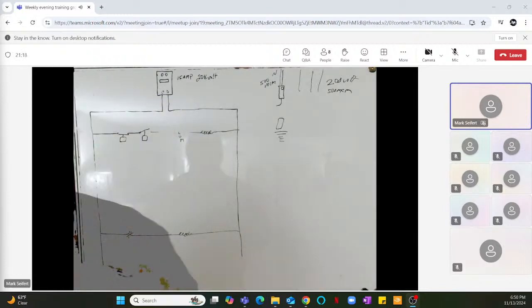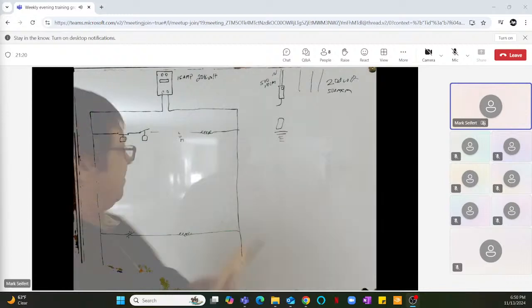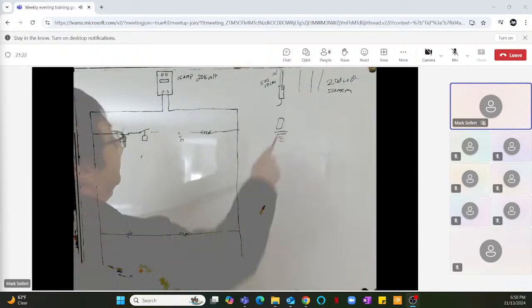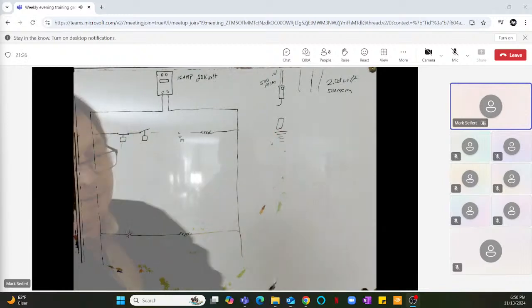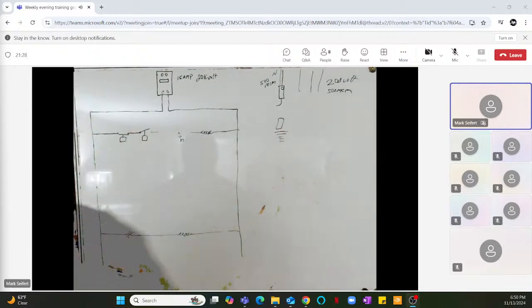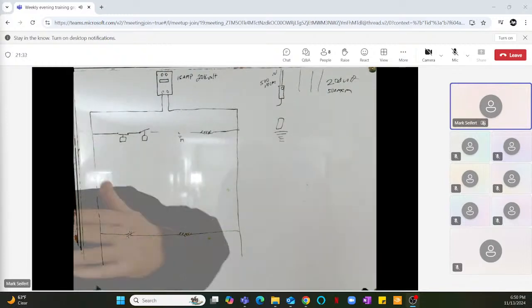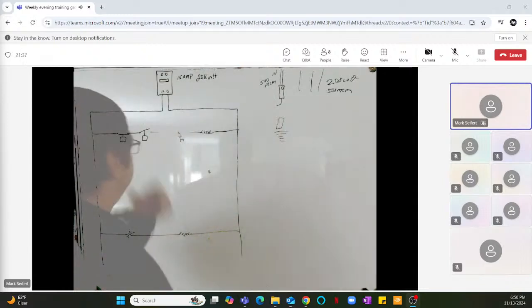And they're much easier to troubleshoot, in my opinion, because you can literally check stuff to ground. You could just hit your ground bar and start checking until you find your open circuit. They're much easier. But for the most part, we are using the 208 volt circuits. So we'll just stick with that.